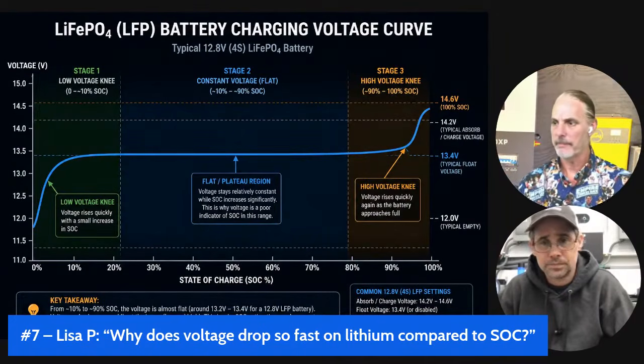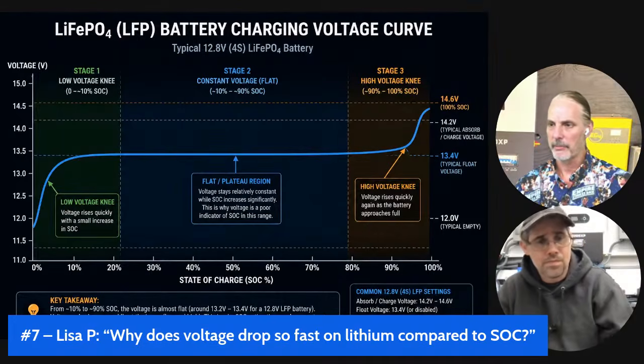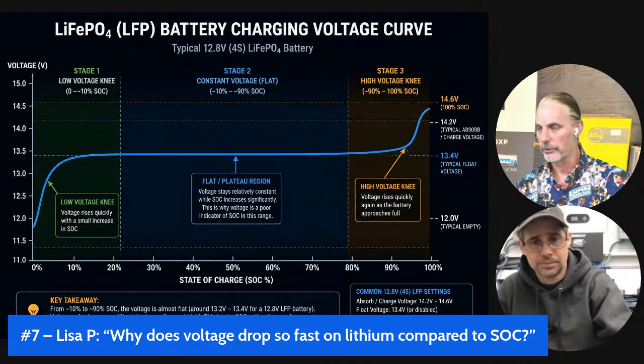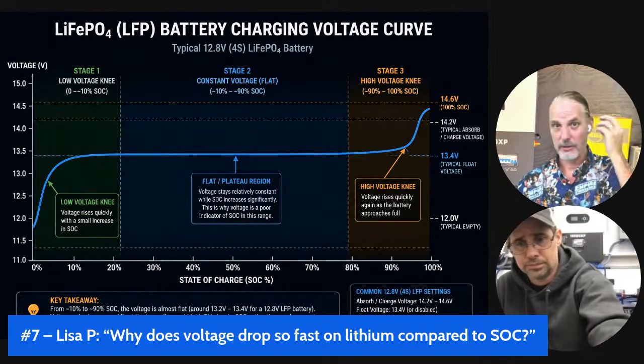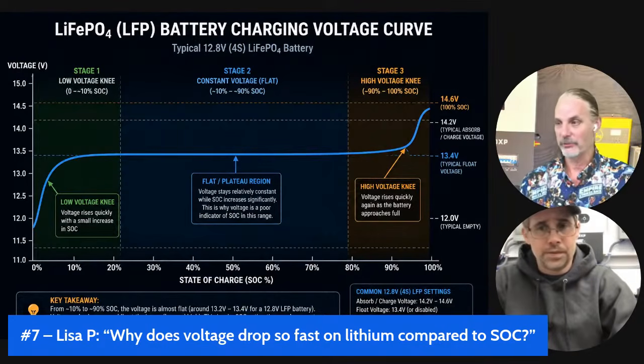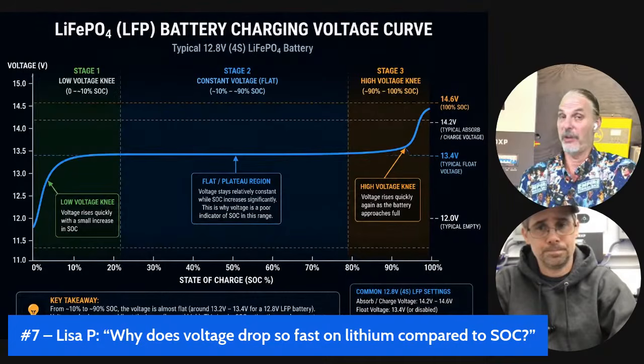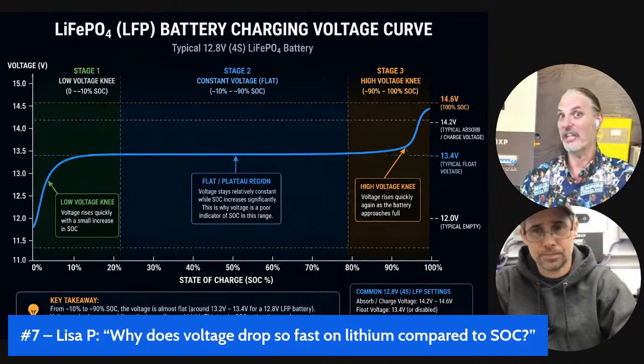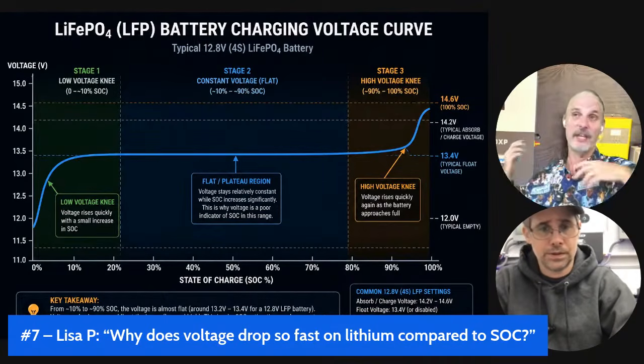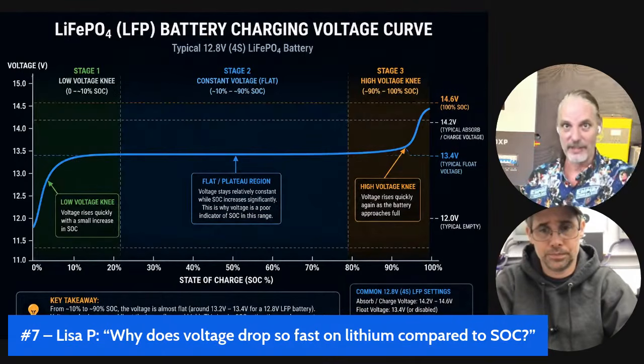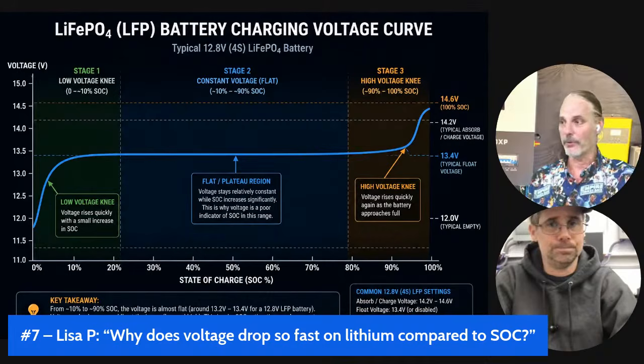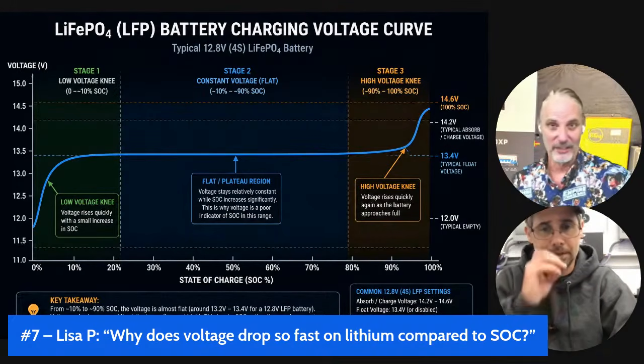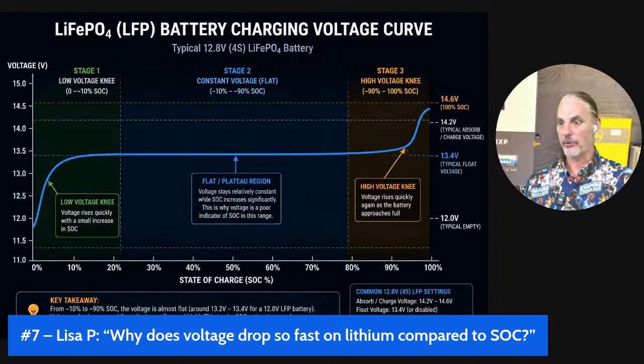Another important point: with lithium batteries, at the very beginning, once your battery is fully charged and you start using it, there's a major voltage drop. You may drop from 56 volts down to 52 or 53 volts fairly quickly within just a few percentage points of state of charge. So you won't see much state of charge change, but you'll see a huge voltage change. Then with a 280 amp hour battery, it may stay at that 52-53 volts for the next 15-20 hours, with very little noticeable change as state of charge keeps dropping. That's the second half of the puzzle: these knees, the last 10% and the first 10%, are where voltage shifts a lot.